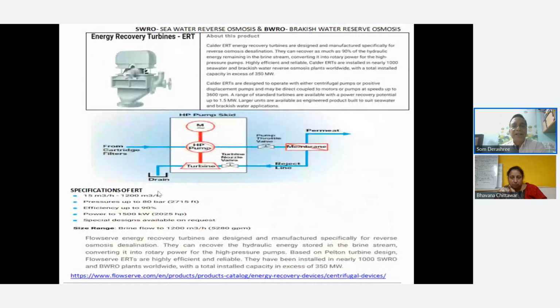Another thing is energy recovery turbines. So what they do is they put a turbine here. Whatever is the high pressure reject, it rotates a pump. There is a turbine here, and you can have an HP pump which is driven through the turbine, or through the motor in case there is some problem here.